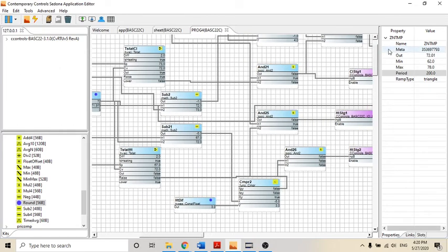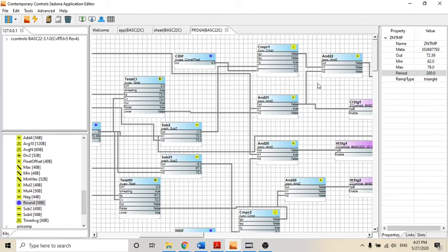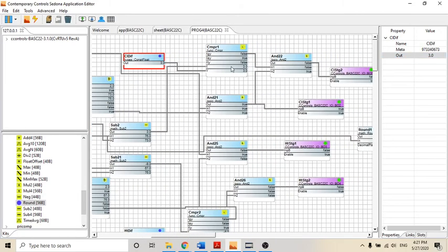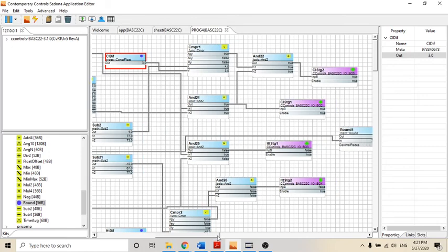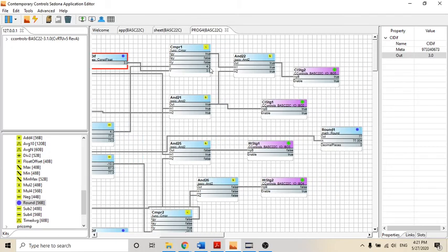The same goes right here. We'll see it with the cooling. We are going to compare. It'll say, is cooling necessary if it reaches more than, in this case, a differential of 4 degrees. So we can change this differential and set it to 3, and that way we'll have the same differential in both. And we are about to see it as the temperature rises. Now they are the same. The block still senses that.